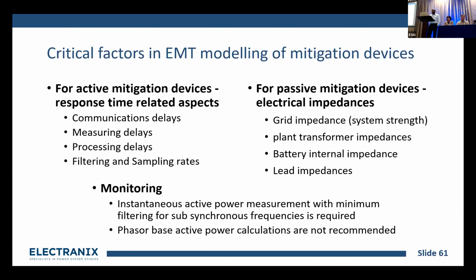those are very important. There are a few important factors we need to be careful about in these models, especially the communication delays, measurement delays, processing delays, and filtering and sampling. Because if you change these delays by even 1 millisecond, your efficiency can drop drastically, and you might change whether you pass or fail.